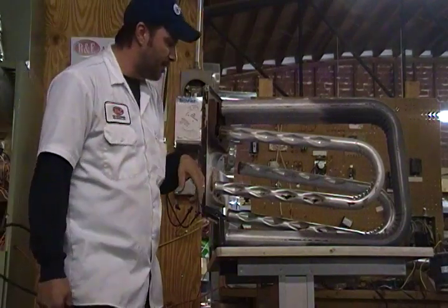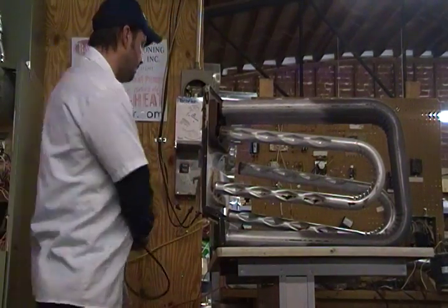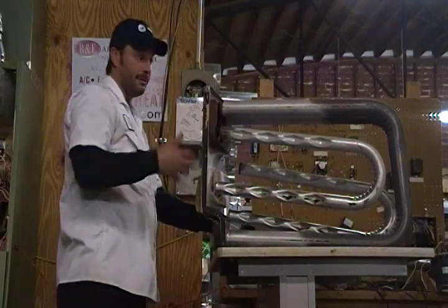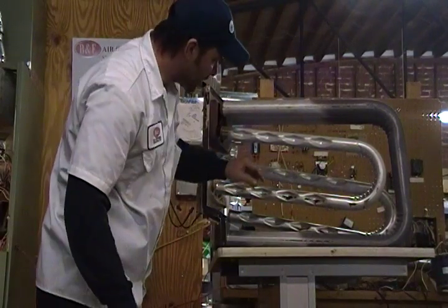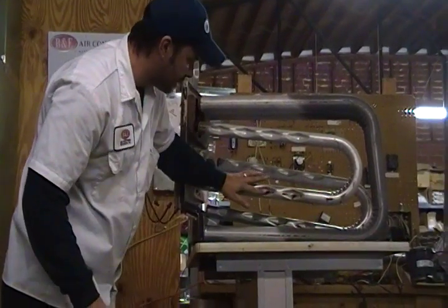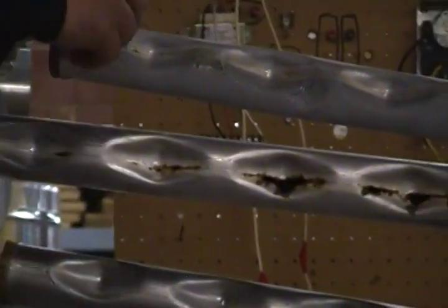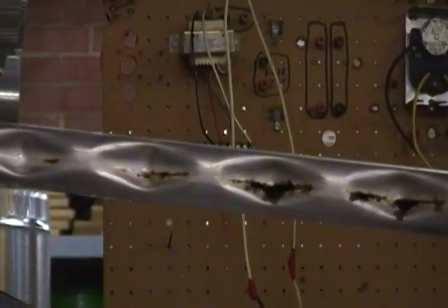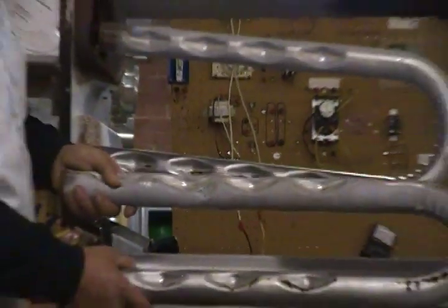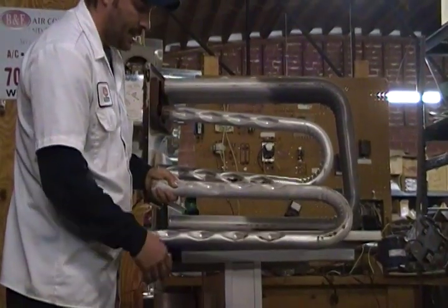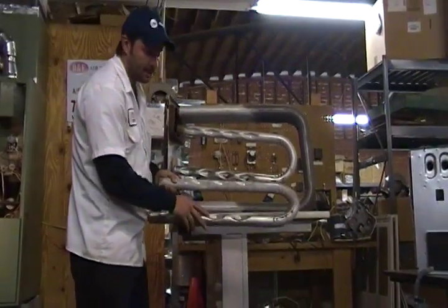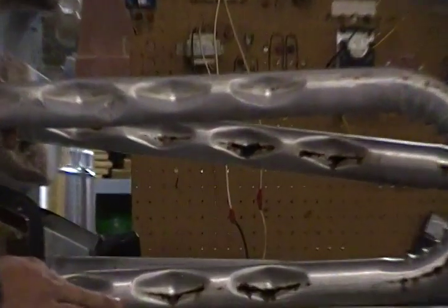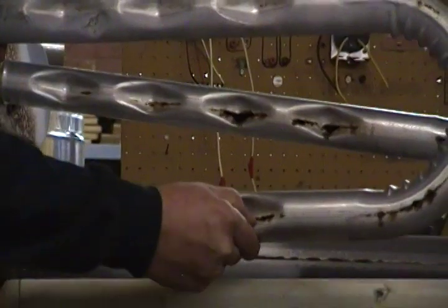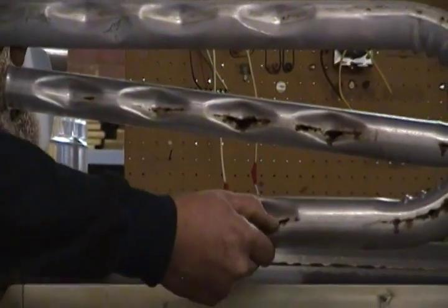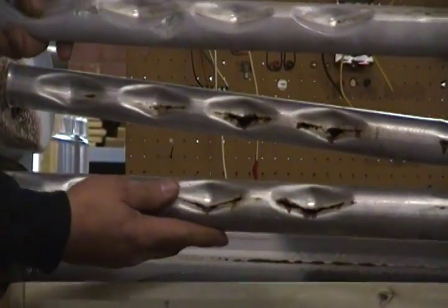So I pulled the top off of it, and what you have here is I come in and started looking at the integrity of the heat exchanger tubes. Clearly what you see here are holes in it. When they make these heat exchangers, they put little weld marks in there when fabricating it, and a lot of times those are the weakest links. If you look right here, these are stamp-outs that they have, and the rust has got to it, along with the heat and moisture, and it has actually rusted it away.